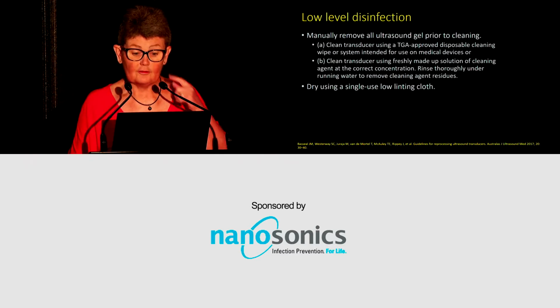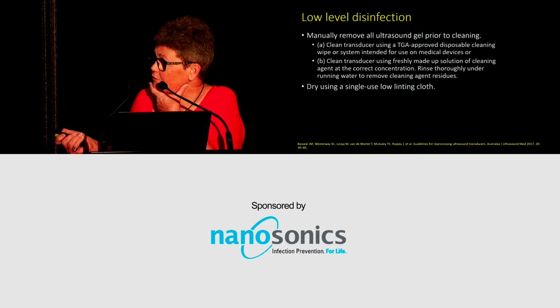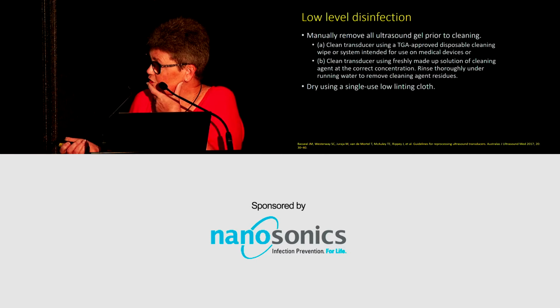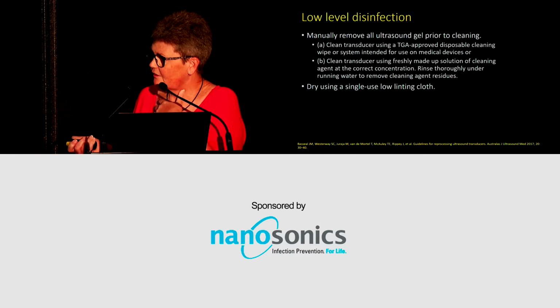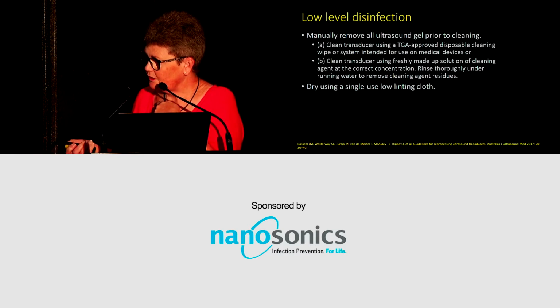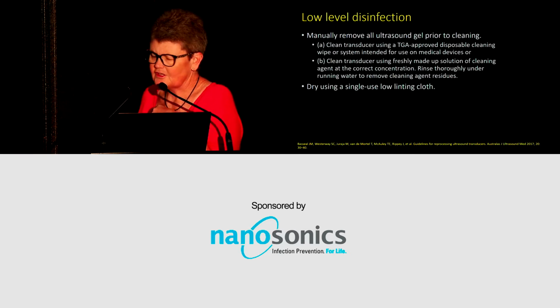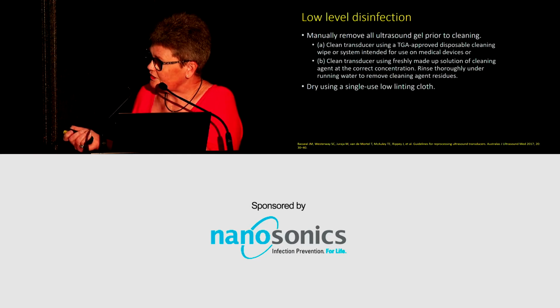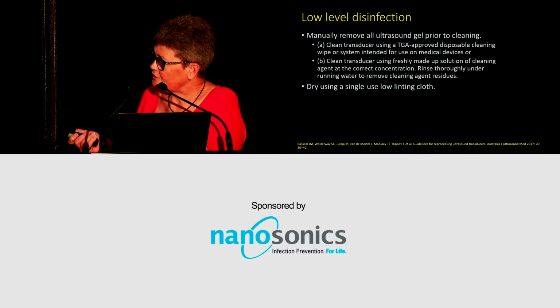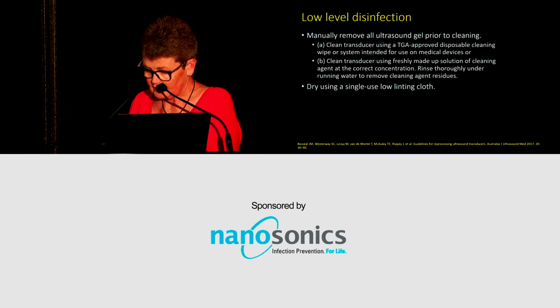So that document outlines low-level disinfection and the procedure for doing that, saying manually remove all ultrasound gel. The transducer is cleaned using a TGA disposable cleaning wipe or system intended for use on a medical device, or clean the transducer by using freshly made up solution of cleaning agent at the correct concentration, and rinsing thoroughly is very important. And then use a dry single-use low-linting cloth for the drying process. So if you're using high-level disinfection, manually remove all gel again prior to cleaning. Make sure you use a TGA-approved disposable cleaning wipe or system intended for use on the device, or clean the transducer using freshly made up solution and cleaning agent, right concentration, rinse under water, and again dry with a single-use low-linting cloth.